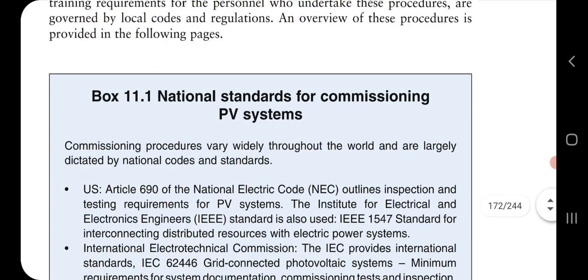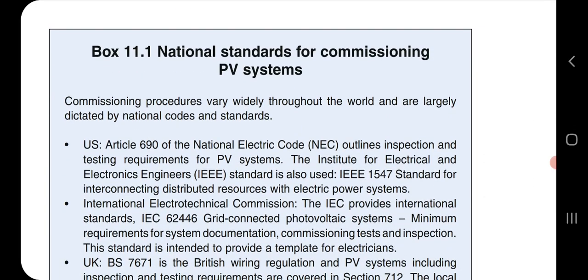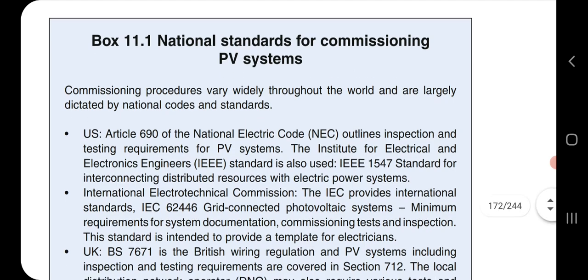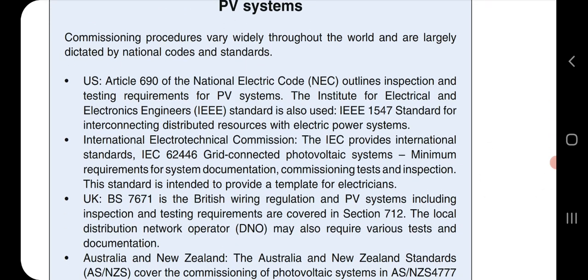So there are some standards which we use, that is, national standards for commissioning. Various countries have their own standards. The first one is the US Article 690 of the National Electric Code, where some testing and inspections have to be done before handing over the PV system. And there are international rules too, like IEC 62446, where testing, commissioning, inspection, documentation, everything has to be done.